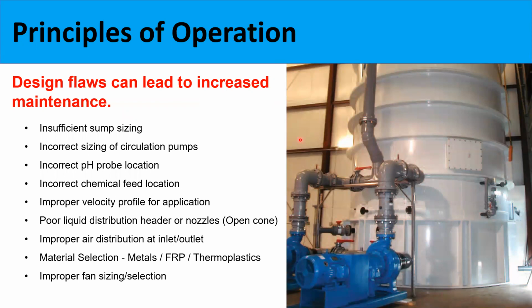So this leads everyone to ask, why am I having issues with maintaining my wet pack bed scrubber? Our experience has shown that design flaws typically lead to increased maintenance issues. These design flaws are typically related to modifications or additions to the process exhaust stream or changes to operations, such as decreased water supply or increased chemical addition. Adding additional exhaust streams to an existing system can also lead to improper velocity profiles in the scrubber, undersized recirculation pumps, or poor air distribution at the inlet or outlet of the scrubber.